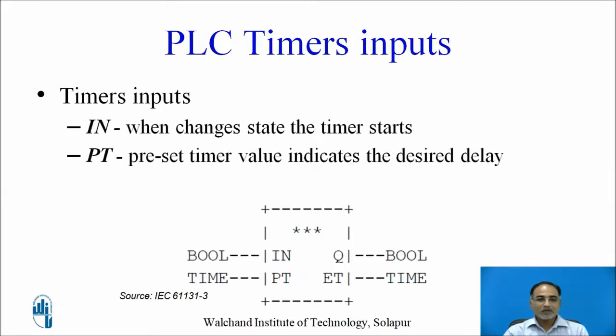Let us learn about the timer inputs. On the function block you will see two inputs represented by IN and PT. When the IN input changes its state, the timer starts counting towards the preset time. The data type associated with IN is boolean, meaning you expect either 0 or 1. The second input is PT, which stands for preset time. This value indicates the desired delay you want in your operation, and its data type is time, meaning you specify the delay in seconds.